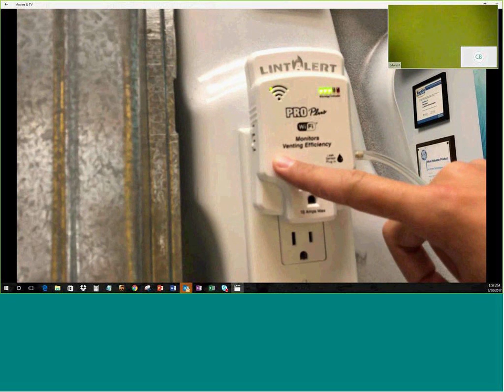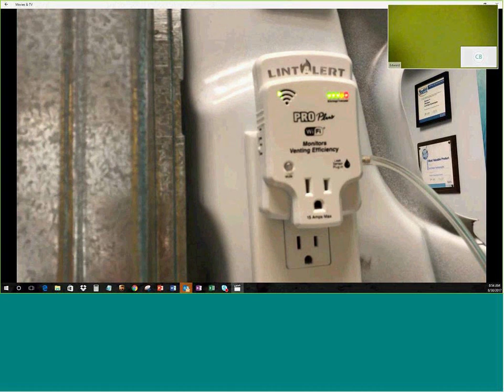Now we can see some added pressure in our system. We have about 0.40 water column inches of pressure, and I'm going to calibrate our LintAlert to 0.40 water column inches. Holding the button in for about 7 seconds, the lights will illuminate 1, 2, 3, 4, 5, and letting go, you'll see the diagnostic pressure check of 3 LEDs blinking.